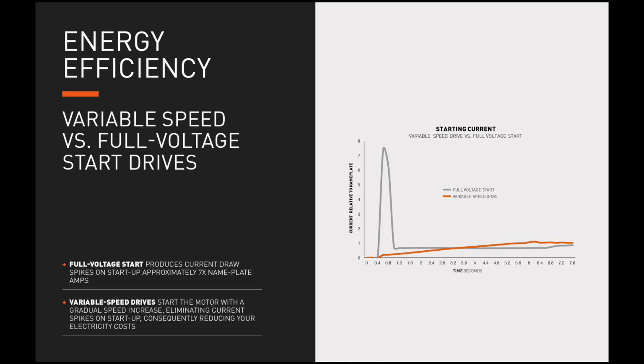Let's move on and talk about variable speed versus full voltage start drives, specifically as it relates to their starting current and energy consumption. The gray line on the graph to the right signifies a full voltage start air compressor, and you can see at the very beginning of its operation that an inrush current spike on startup is evidenced. This inrush current spike is typically 7 times the current displayed on the nameplate. Comparatively, the orange line signifies the startup current profile of a variable speed drive air compressor, and you can see that the variable speed drive starts the motor with a gradual speed increase, eliminating any inrush current spikes on startup, consequently reducing your electricity costs.